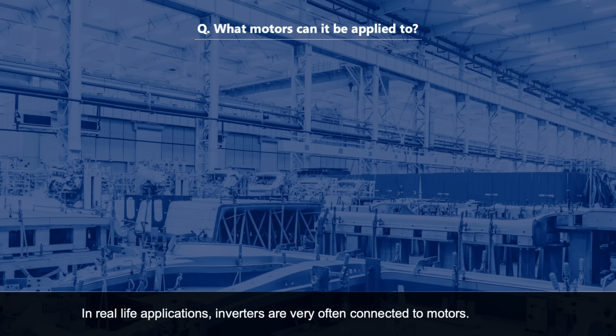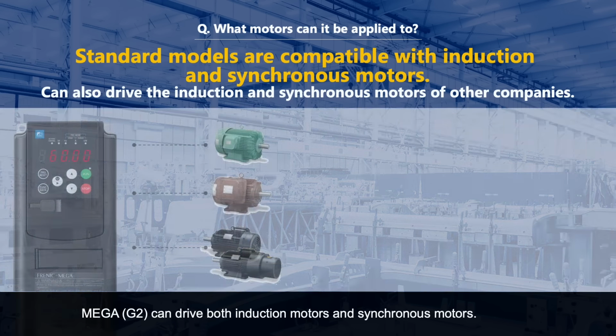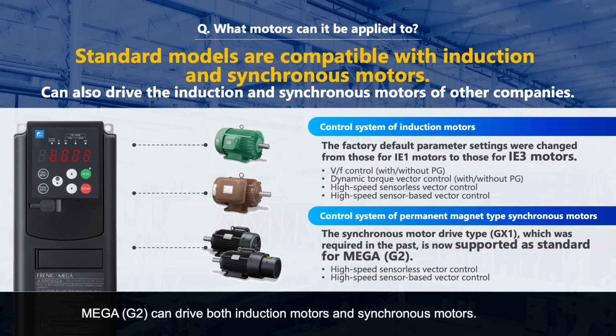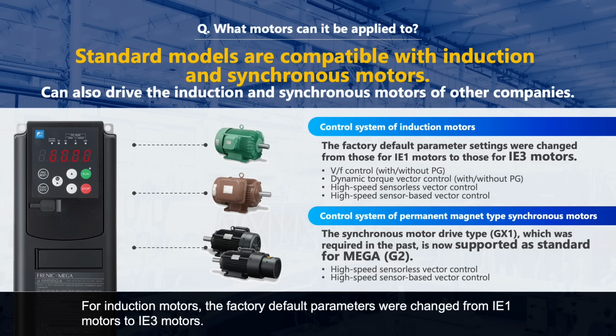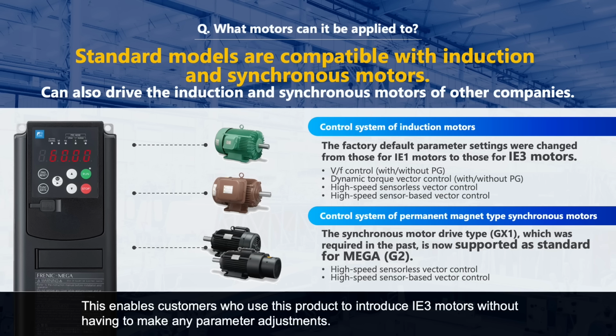In real-life applications, inverters are very often connected to motors. Therefore, compatibility with motors is very important. Mega G2 can drive both induction motors and synchronous motors. For induction motors, the factory default parameters were changed from IE1 motors to IE3 motors. This enables customers who use this product to introduce IE3 motors without having to make any parameter adjustments.